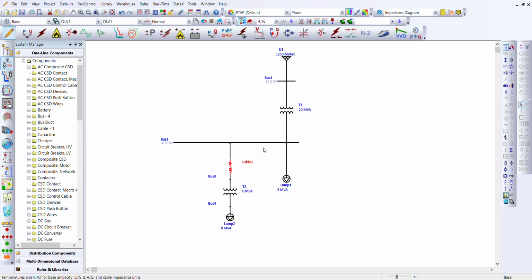The specification says NEC EPR 133%, 5.0 kV magnetic, 3-core copper, and the size is 4/0. Now, length is 200 feet. We have already put that. So now remember, we're in a frequency of 60 Hz, so we will not use a 50 Hz cable. Now we are in 60 Hz.